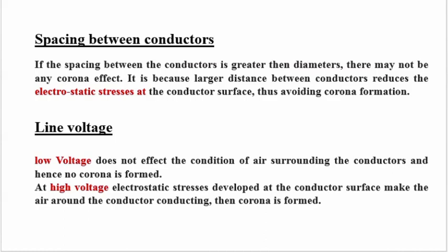In simple words, by increasing the spacing between the conductors, we are increasing the air between the conductors, and by increasing the air between conductors, we are introducing a higher dielectric medium, and as a result the capacitive effect will decrease, and the ionization of air will be reduced, and as the ionization of air is reduced, the corona formation will also be reduced.